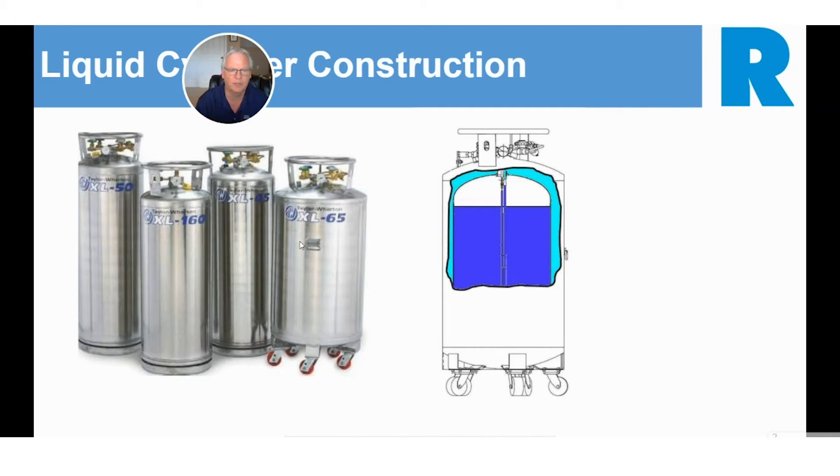The liquid normally is going to lose one to 2% a day in a liquid cylinder. And without the vacuum, it's going to lose its contents within a day. It's just going to be boiling off. It's almost like pouring liquid nitrogen or oxygen or argon into a bucket and letting it sit there and boil off. It dissipates pretty quickly.